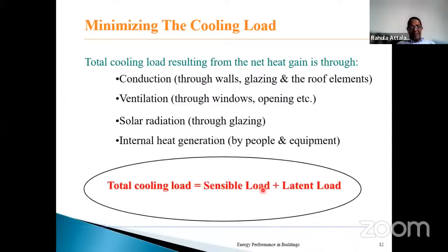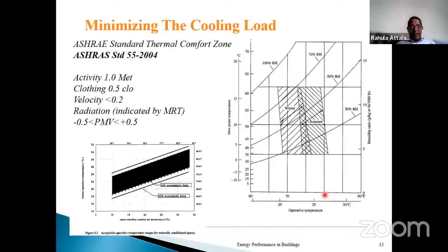And this interaction, the total cooling load, is generally divided into two: sensible cooling load and latent cooling load. Sensible cooling load talks only of a change of temperature. Latent cooling load doesn't talk of the temperature, but is based only on the moisture level, that is, adding or removing moisture into the interior of the building. So these are the four elements. And this is the standard for minimizing the cooling load.